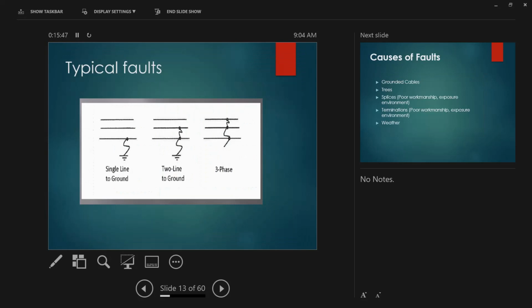Now, typical faults. You see the single line to ground, which is one line to earth, probably a breakdown of insulation or of a post insulator on the pole. Or two line to ground, where you drop some kind of metal over there and it breaks down to ground. The other one is three phase, which means you short or bridge the three phase lines. That's the kind of fault that we typically see in that part of the industry that we discussed earlier.